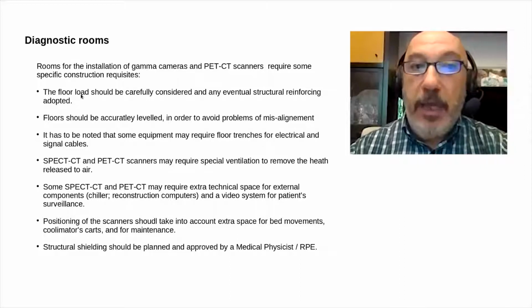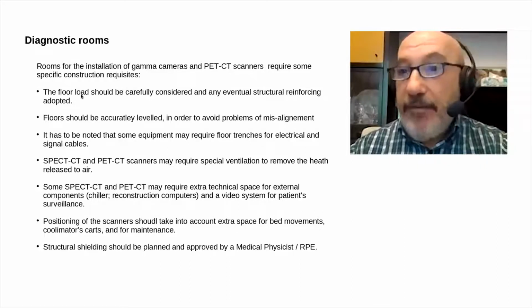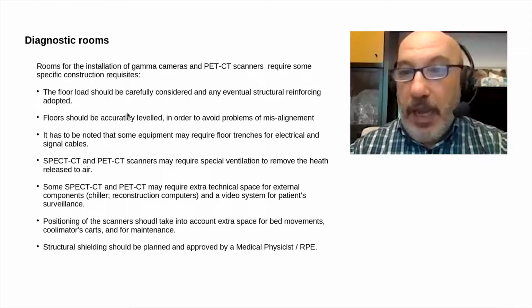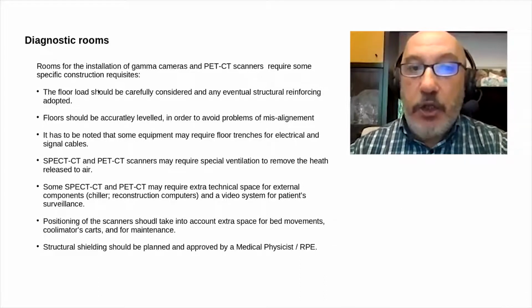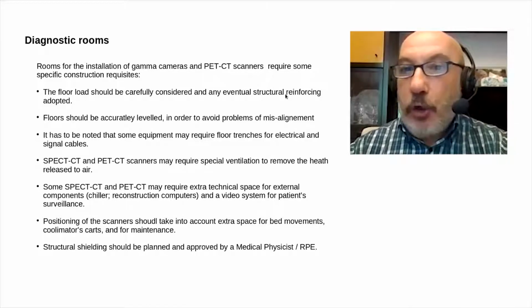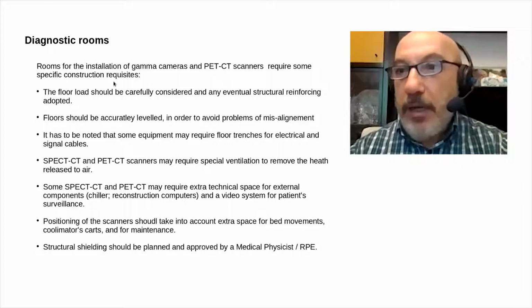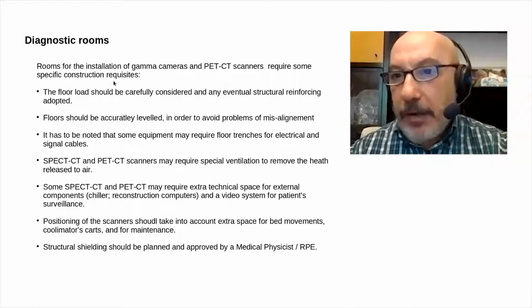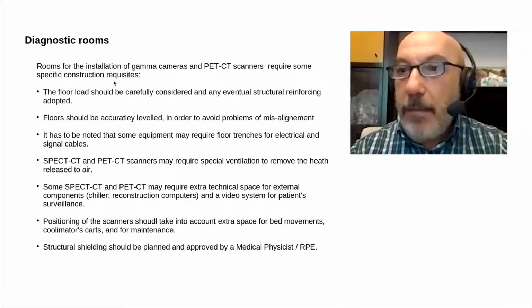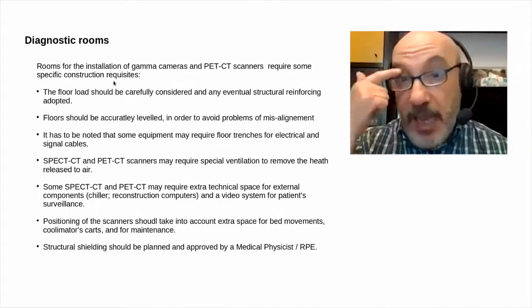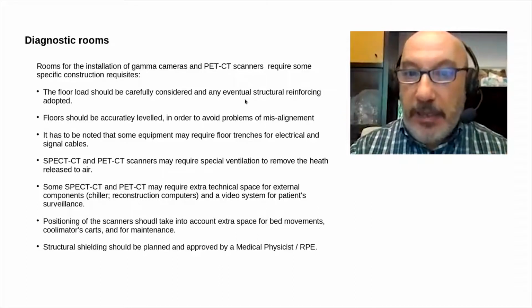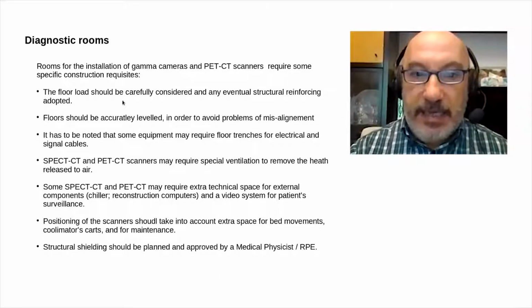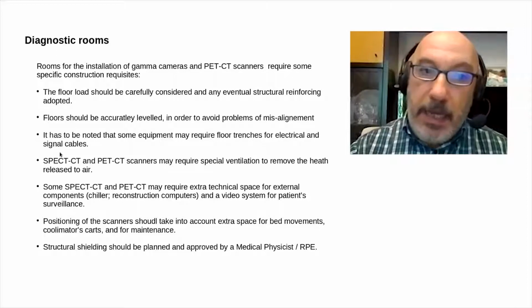But apart from shielding, the diagnostic room has a lot of requisites. In particular, the floor should be carefully leveled in order to host the scanners properly, and should be reinforced in order not to present any structural problem when hosting a scanner that may weigh more than 2 tons, maybe around 3 tons, concentrated in about 1 square meter, so that particularly resistant floors are necessary.